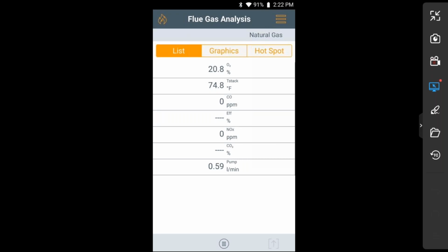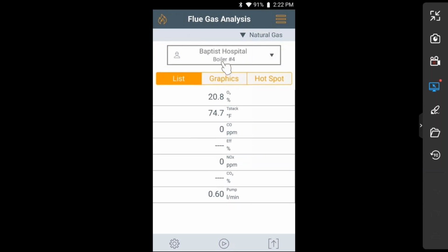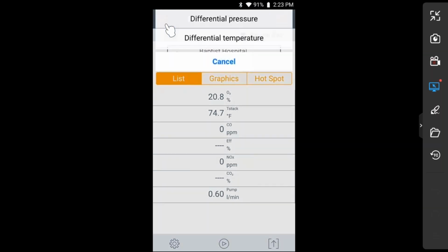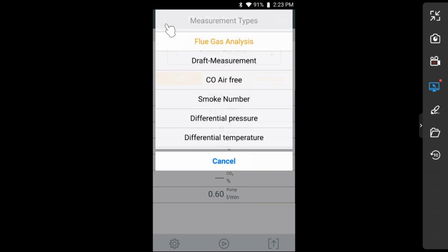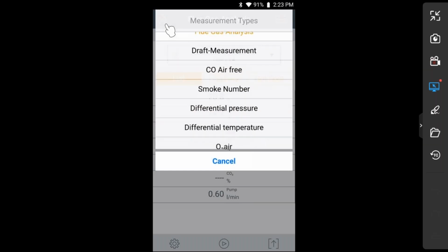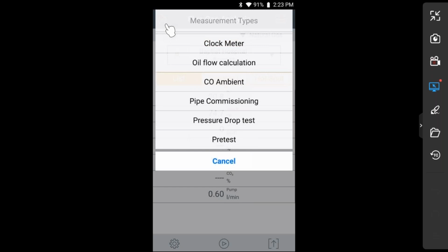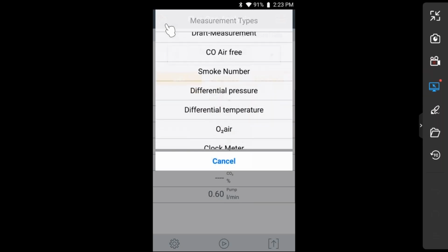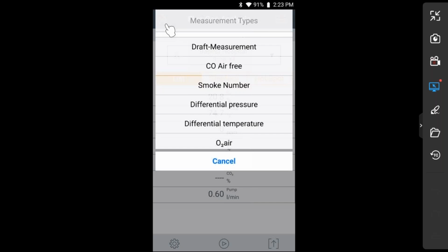This is an easy instrument to operate. The center button below here is my on-off button for my internal pump. I just shut off my internal pump, and you'll see the display saying the location I'm at, boiler number 4. Over here, if I push the fuel button, the measurement type button, you'll see that I have a lot of different measurements that I can do with this analyzer. Some of these measurements will not pertain to your market. Others pertain more to the European market.